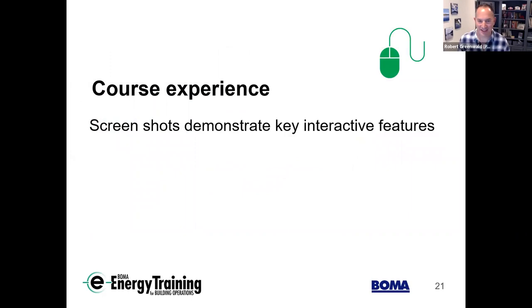Thanks Christine and Damien. I've been practicing energy management since my days as a co-op student. One of my first projects was working in Toronto for an energy management firm called Energy Interface. We had a performance contract with the Waterloo County Board of Education, and going in to interview building operators, we found schedules programmed from 0000 to 2359 — everything running essentially flat out all the time. That opened my eyes to the potential for getting operators involved. We focused on building operator manuals, training, interactions, and competitions to really harness the knowledge of building operators, which is what we're trying to do here with this online course.